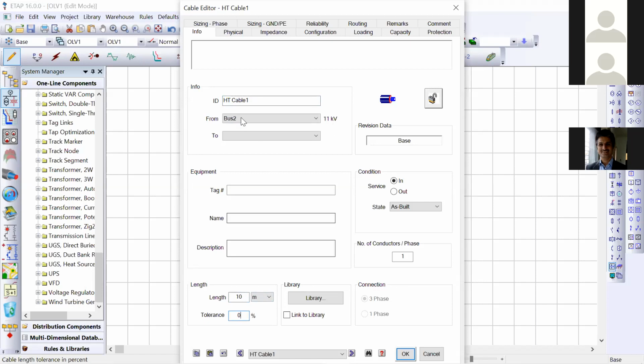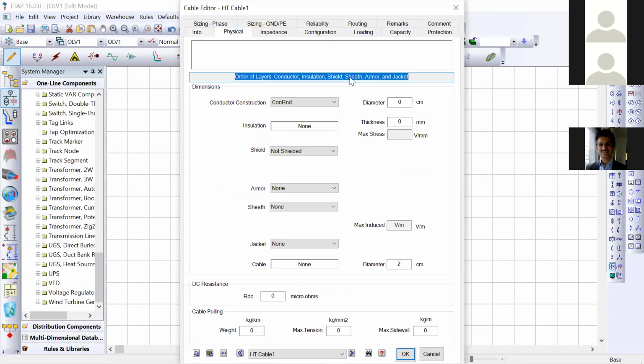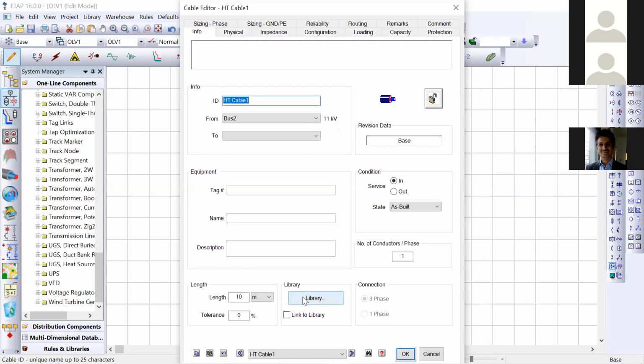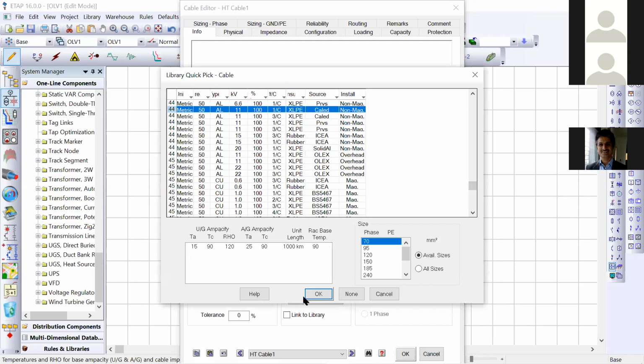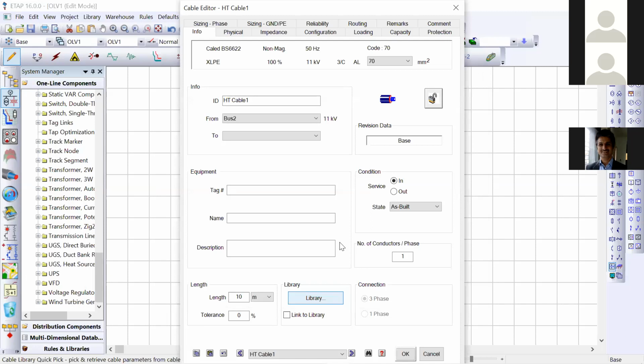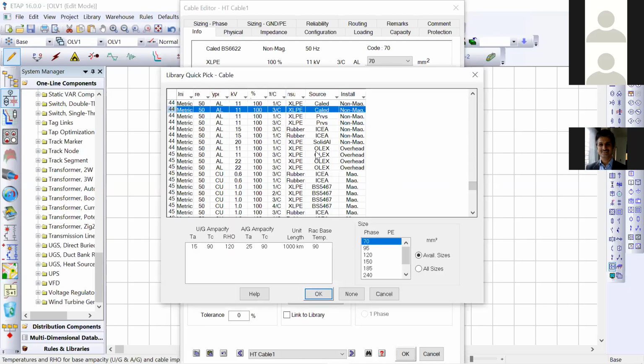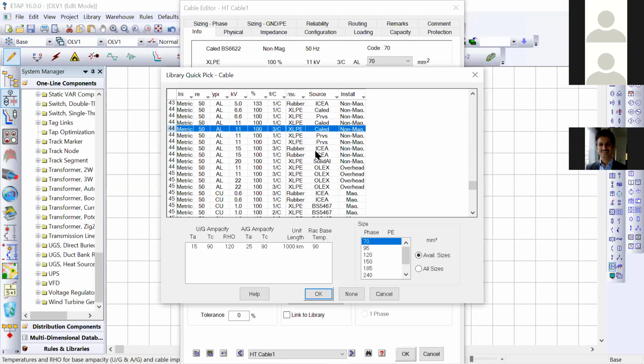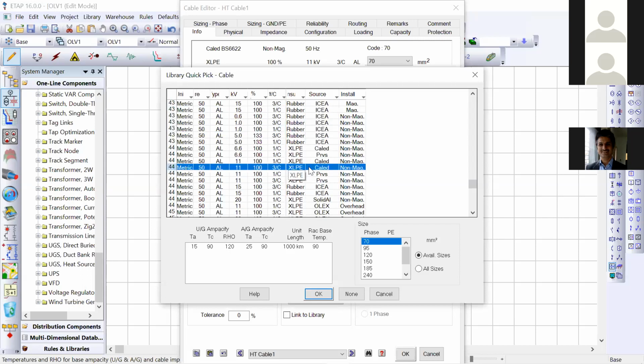Now, either I can give all these details on my own, or I'll select the cable from the library. ETAP has an inbuilt library for various categories of elements. In this particular case, this is a 3-phase connection, a 3-phase cable. So I'm taking a 50 square mm aluminum conductor, 11 kV cable, 3-core XLPE insulated, non-magnetic cable. I can go with any of these, but that device must be suitable to my loading requirement. So presently I am going with the 50 square mm 11 kV 3 core XLPE cable.